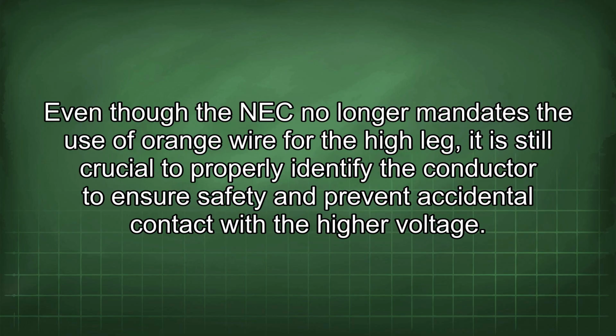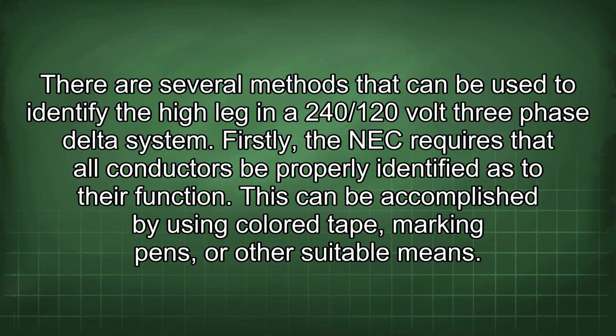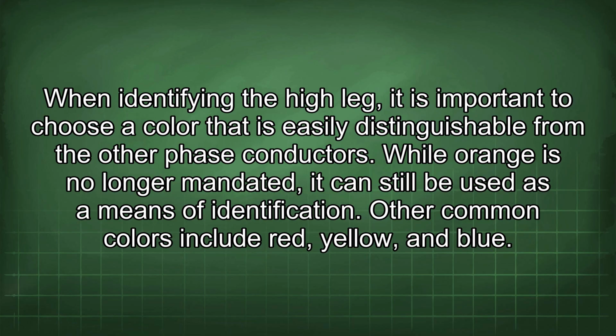Even though the NEC no longer mandates the use of orange wire for the high leg, it is still crucial to properly identify the conductor to ensure safety and prevent accidental contact with the higher voltage. There are several methods that can be used to identify the high leg in a 240/120-volt three-phase delta system. Firstly, the NEC requires that all conductors be properly identified as to their function. This can be accomplished by using colored tape, marking pens, or other suitable means. When identifying the high leg, it is important to choose a color that is easily distinguishable from the other phase conductors. While orange is no longer mandated, it can still be used as a means of identification. Other common colors include red, yellow, and blue.